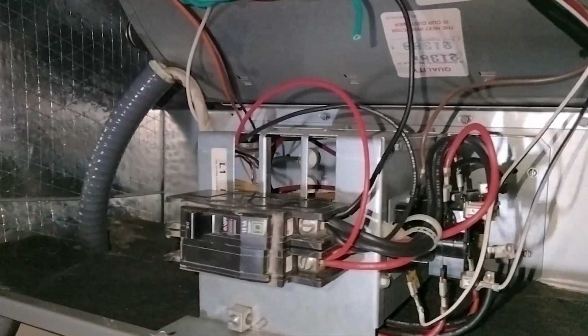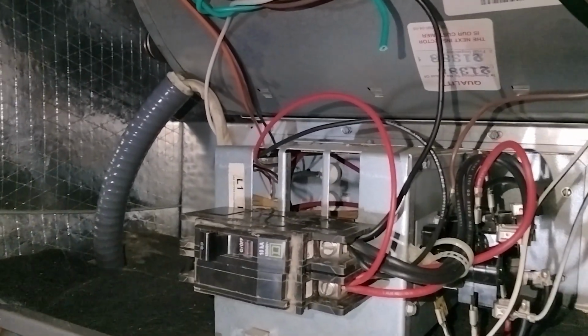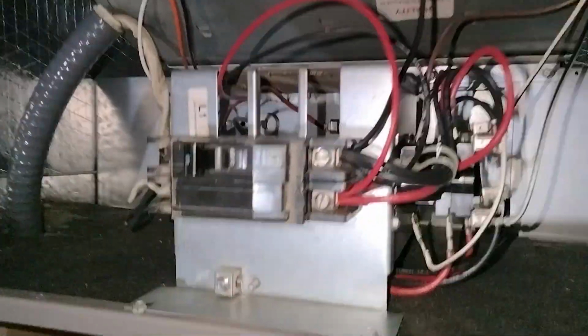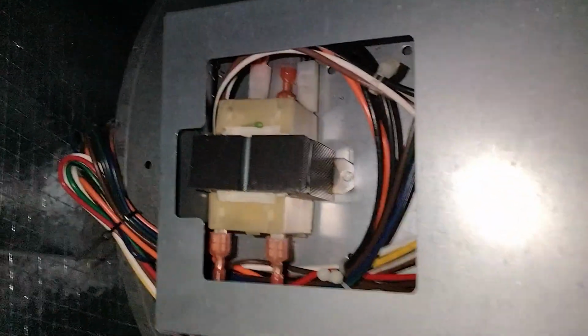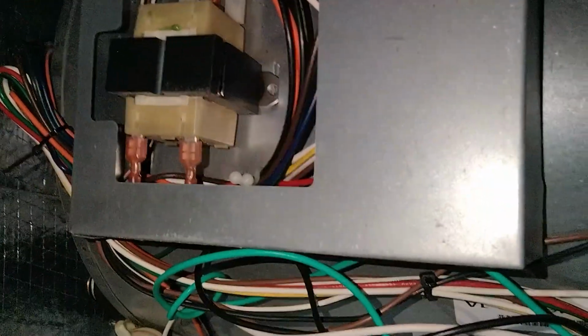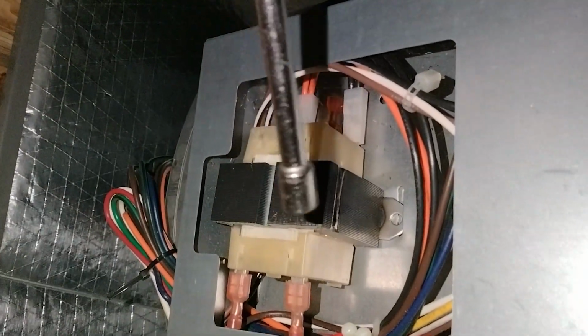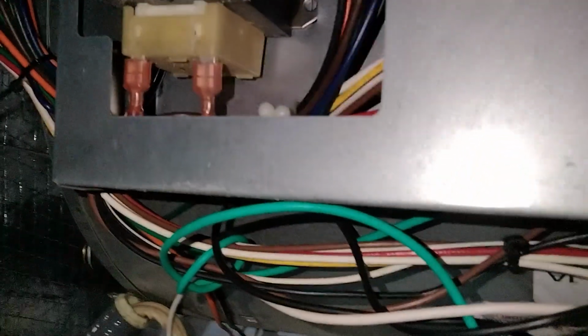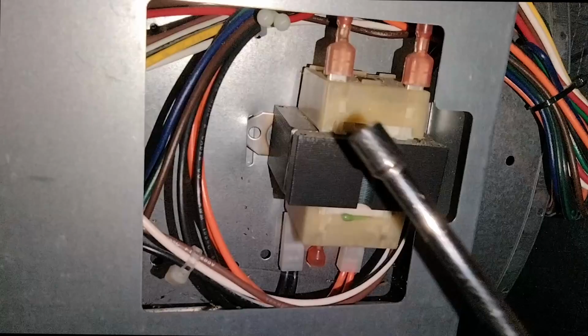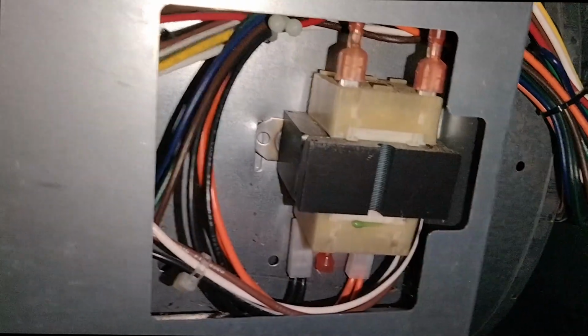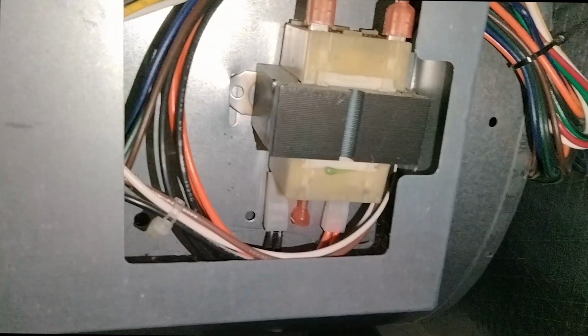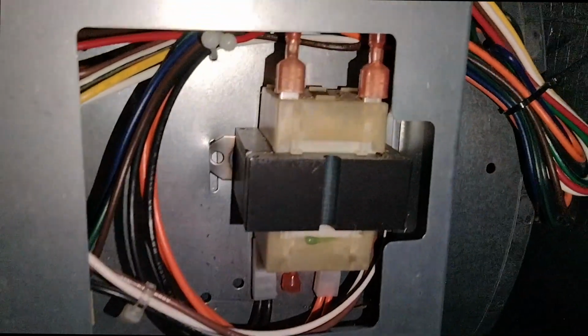Now, this might look different than what you've got. Remember, every piece of equipment is unique, brand to brand. They've got their own design, and then, of course, the age of the unit comes into factor. So as you can see, we've got our transformer here, and it will be labeled on one of your sides. This one's got a sticker over here that you can't see. They could look different, but they're all going to have this core here with the 2 high side power wires coming in, and then of course the 24-volt side coming out.